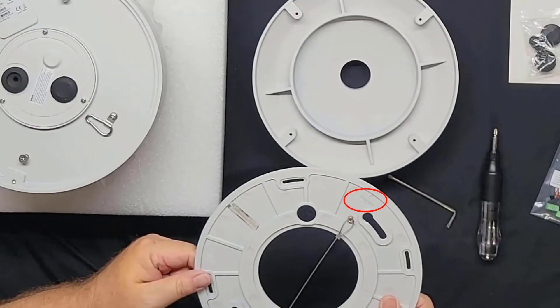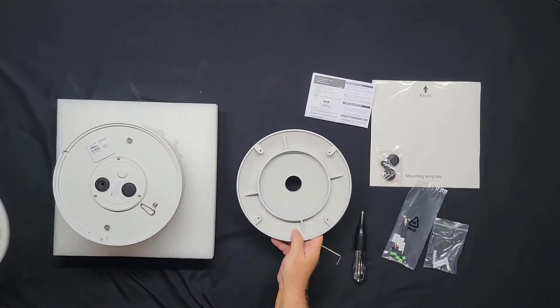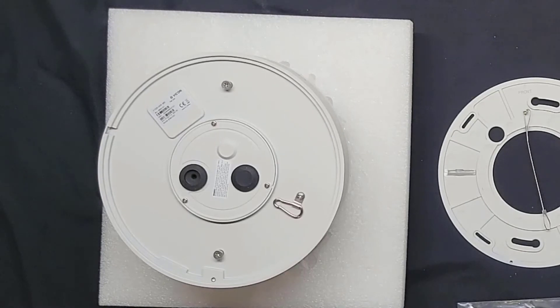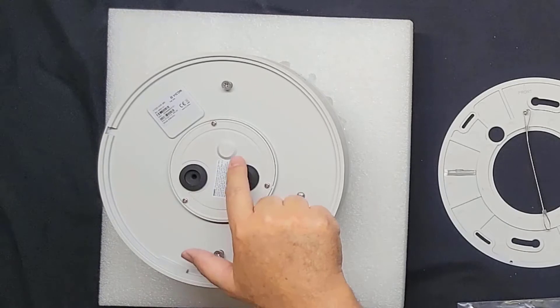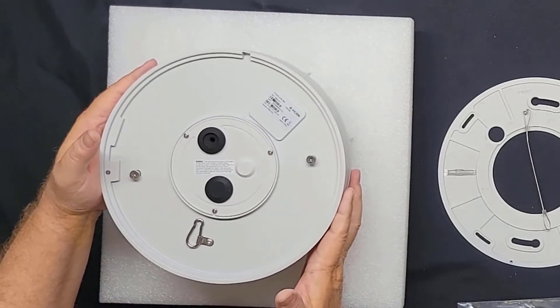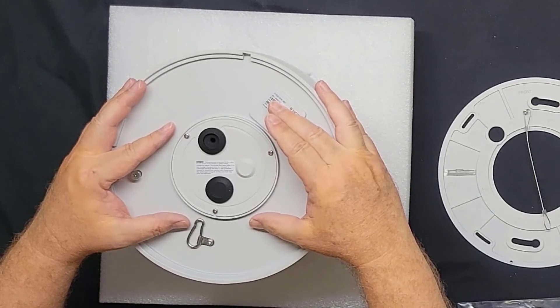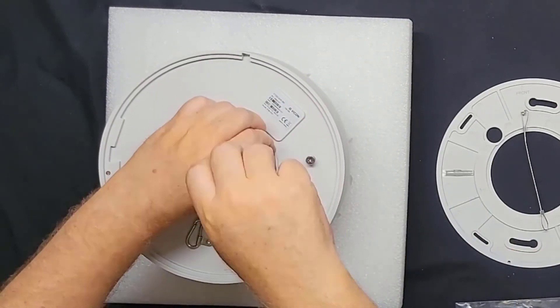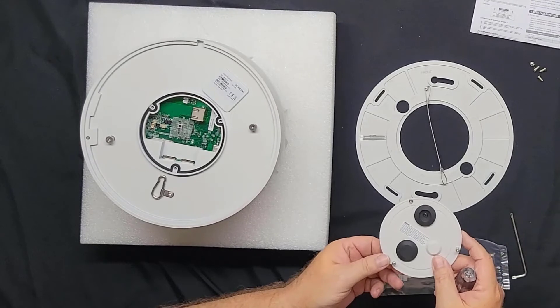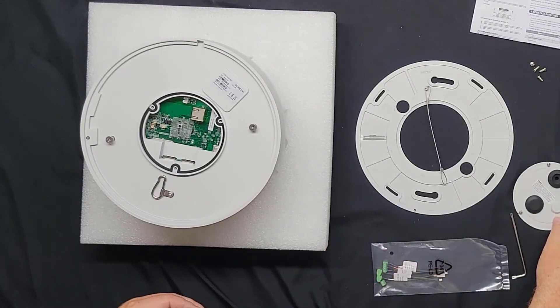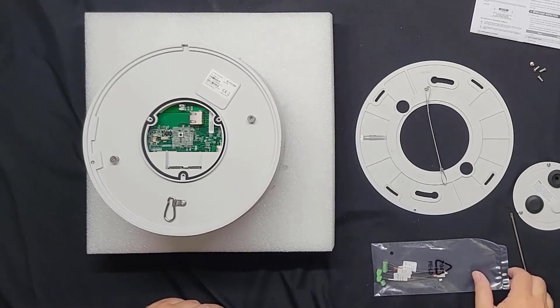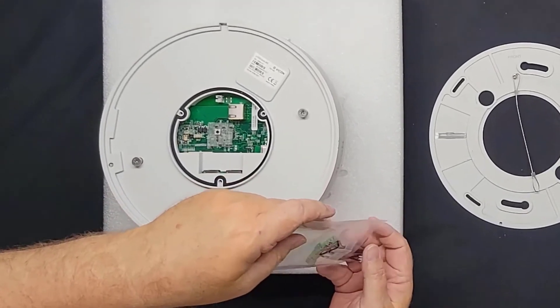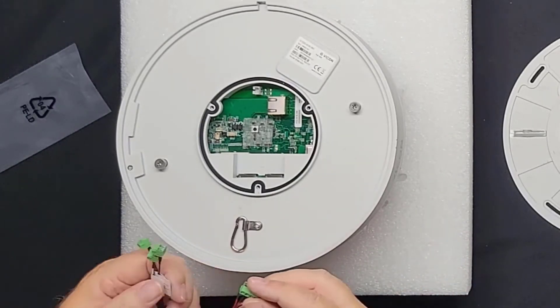Like the packing foam, be sure to save those four screws or screw them back into the cap as you might need them in the future. In the center of the camera, we see an access plate with two grommets, one solid and one with a hole in it. This is for passing through an un-terminated ethernet cable. In the spare bag, there is another grommet with a hole in it that you could use to replace the solid one. You would do this if you were using audio, alarms, or direct power.